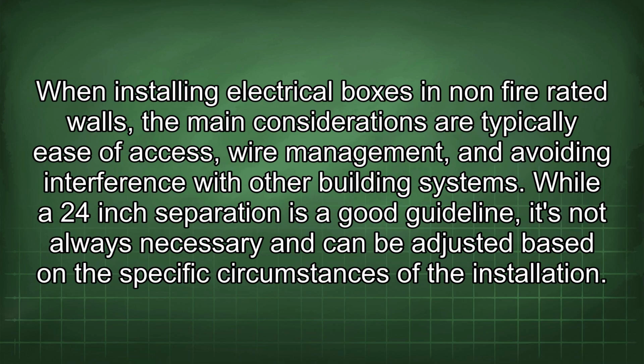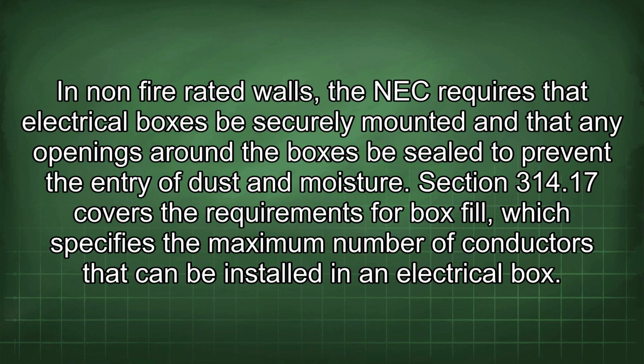When installing electrical boxes in non-fire-rated walls, the main considerations are typically ease of access, wire management, and avoiding interference with other building systems. While a 24-inch separation is a good guideline, it's not always necessary and can be adjusted based on the specific circumstances of the installation. In non-fire-rated walls, the NEC requires that electrical boxes be securely mounted and that any openings around the boxes be sealed to prevent the entry of dust and moisture.